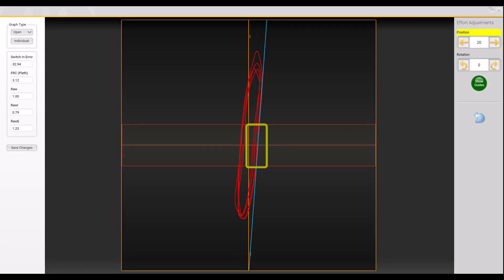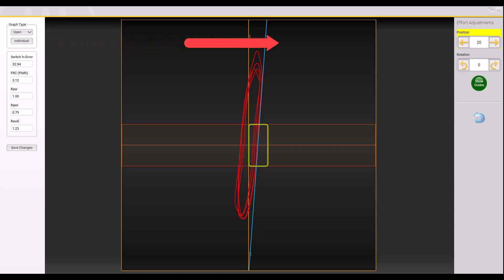Experts will tell you that one of the most important points to remember is consistency when adjusting the line of best fit — consistency from patient to patient and visit to visit. It is also recommended to move the line of best fit to the right side of the open shutter tracing. The position adjust arrows in the upper right can be used to move the line to the right or to bring it out if hidden within the red trace.